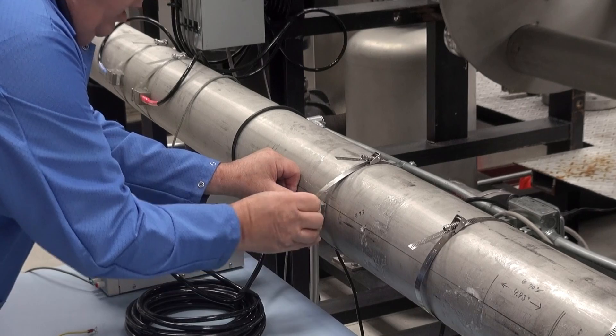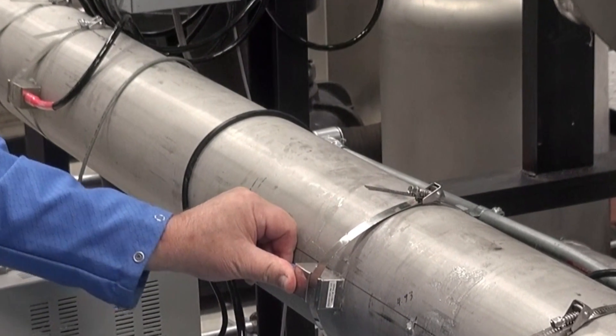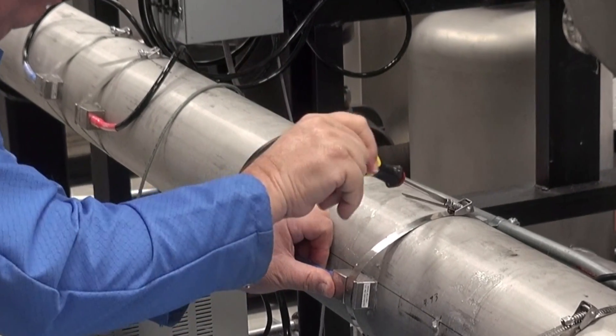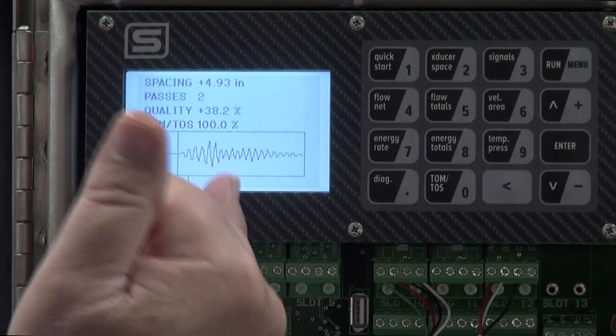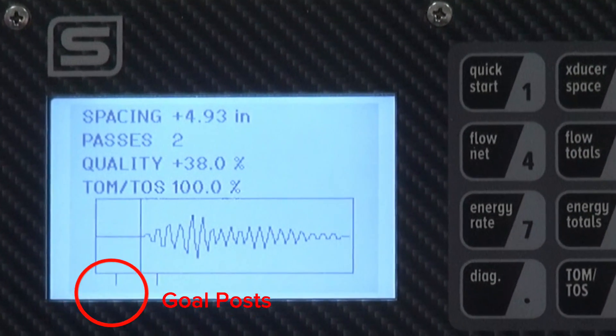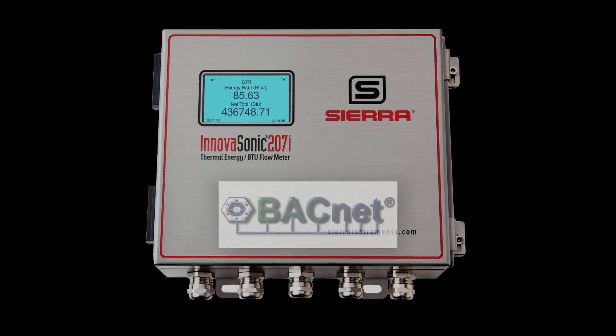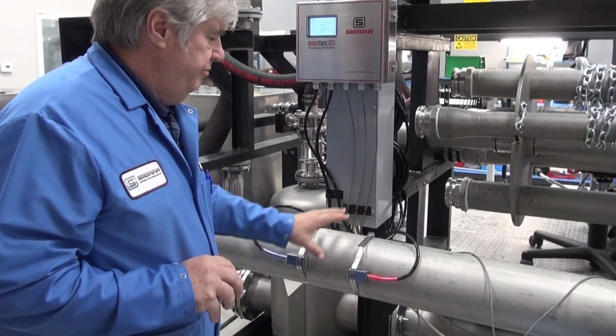Sierra has focused on making clamp-on transducer installation as easy as possible. The InnovaSonic 207i features a large backlit display and dual function keypad with audible feedback. With clamp-on sensors there's no pipe cutting or expensive plumbing. The 207i has a visual sensor spacing tool on the display — slightly move the sensors together or apart so the indicator line is between the goal posts. Easily connect the InnovaSonic to your building management system with BACnet communications. With its robust stainless steel enclosure, permanently fasten the transducers to make it a hardened installation and you are ready to measure.